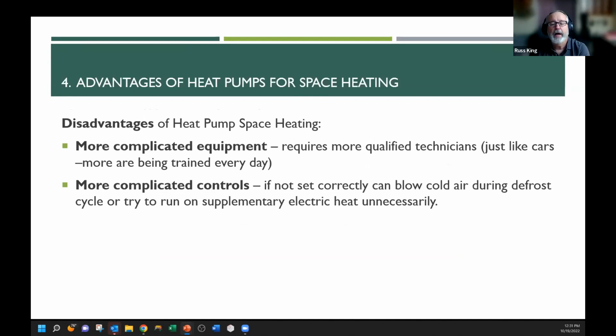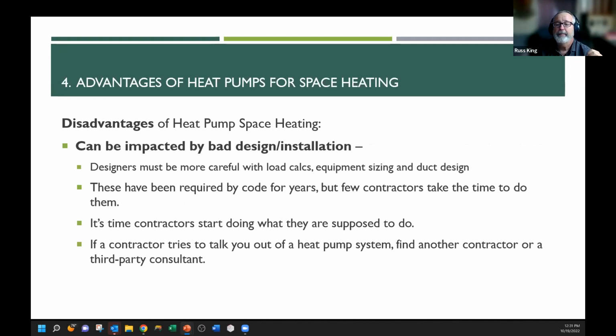All right, disadvantages. The equipment itself, the controls and things like that, are more complicated. It does take a little bit higher level technician to service some of these things, but that's getting better every day. If you don't correctly set the controls, they may actually blow cold air during a certain time of the day, which is not good, but that can be overcome. These are all preventable disadvantages. They can be impacted by bad design. A gas furnace is a dumb beast. You put it in a house, it blows heat into the house. Heat pumps are like air conditioners, in that the actual heating capacity depends on the design conditions.